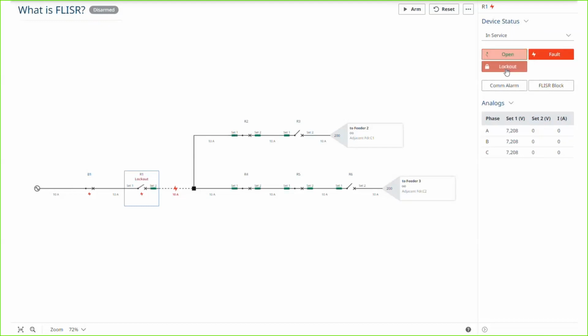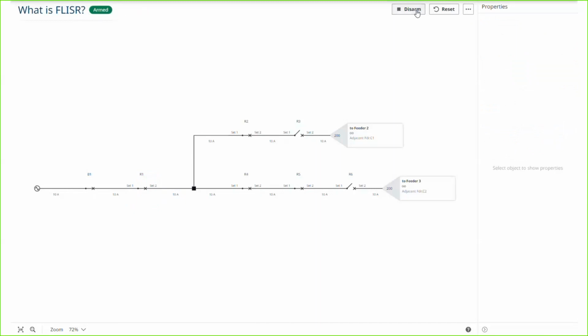And you can see I'm just driving this using the integrated simulator in FLISR. So we're going to be in the product for the rest of this presentation. So what you have here now is an outage, right? Everything downline of recloser 1 is experiencing an outage. The green boxes are PTs, telling you that the voltage is dead. The line is de-energized downline of that recloser.